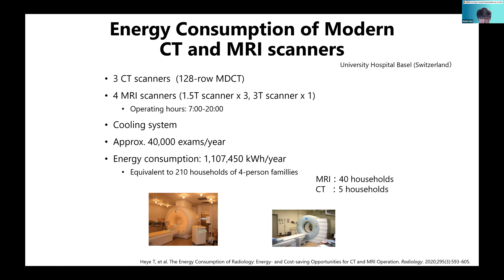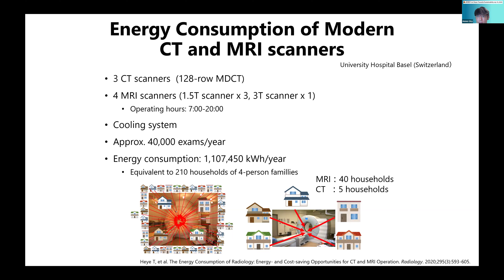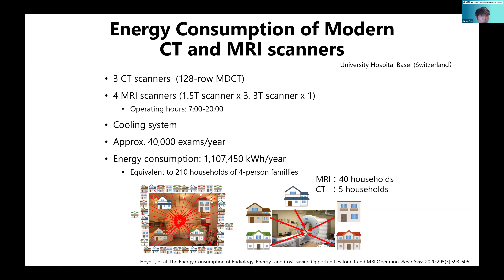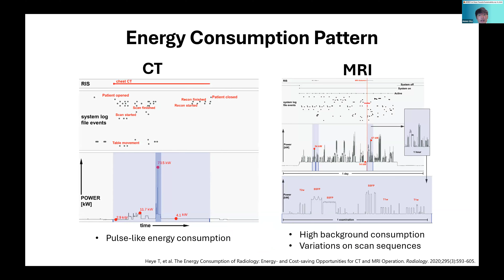The annual energy consumption is enormous, equivalent to power consumption of about 210 households. For instance, one MRI unit consumes energy equivalent to 40 households and one CT scanner to 5 households. Here are energy consumption patterns of CT and MRI. CT scanners show pulse-like energy consumption during image acquisition, whereas MRI consumes a high proportion of energy even during idle times.